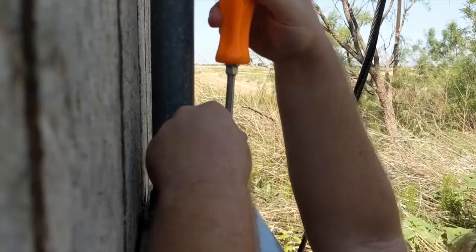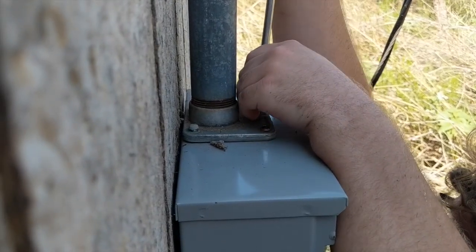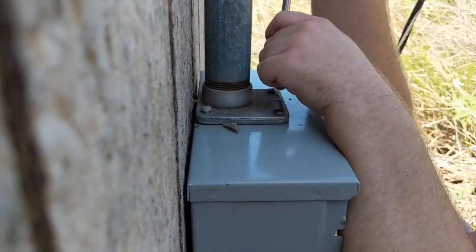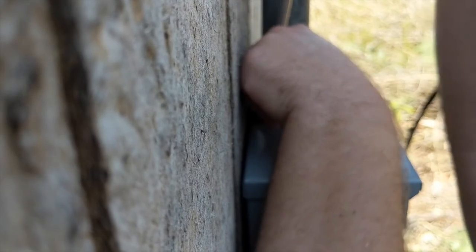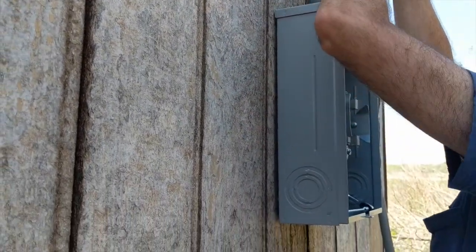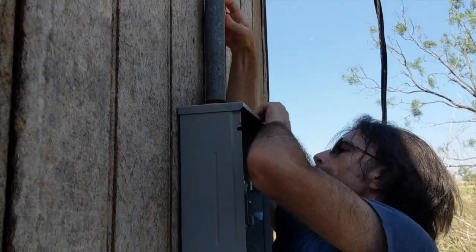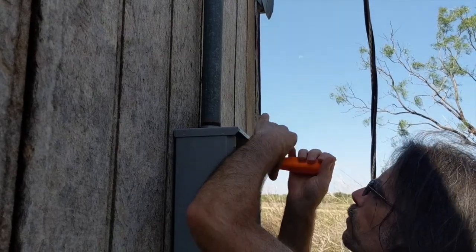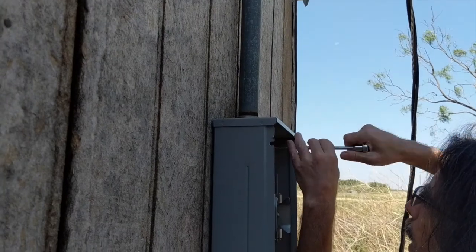You make it easy, don't they? Get the back ones first, get them all finger-tight first. That's good. Wow, it actually - that old of a hub, probably 20 to 30 year old hub, and it fits perfectly in the brand new meter base which is actually manufactured in 2018. That's just nuts. This back one seems to be going. Thread everything in, then lock it down.